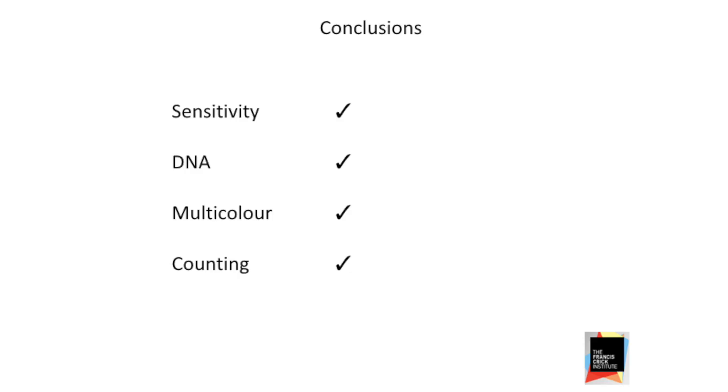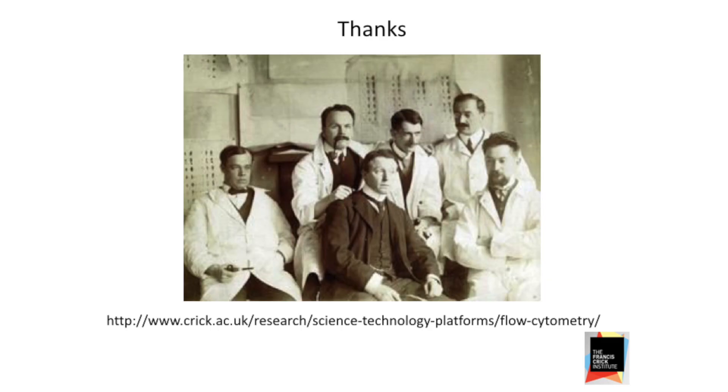So that's all. We checked the sensitivity of the NovoCyte — very good, as good as the other machines in the lab. Very good for DNA: the linearity and CVs on our DNA peaks are very good. Multicolor phenotyping with three lasers and 13 colors covers probably 90% of what people are going to want to do, certainly in my lab. And it's a very good absolute counting machine. This information will eventually make it to our new website.